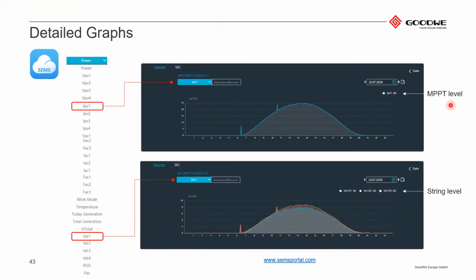Okay, now. So clicking on this curve setting, you will get to this page. It will look like one of these. So here are 2 different examples. Here on the top side, you have selected the current for PV input 1, string current in the first string. Here you have selected the current for the MPPT, and here it is for the string.